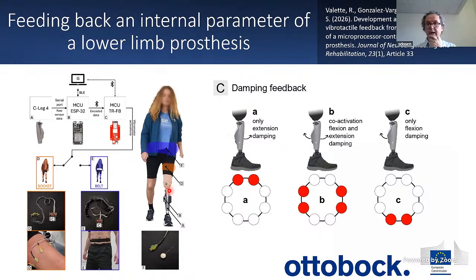It's a C-Leg. We have access to the internal states of the leg. And we decided to provide vibrotactile feedback on the damping of the knee. So this microprocessor knee is intelligent, and as you walk, it changes the damping, stiffening up in the flexion direction, stiffening up in the extension direction, or stiffening up in both directions. It's an internal parameter, and we decided to provide information about this internal parameter by transmitting dedicated stimulation profiles. So three stimulation profiles to the subject.